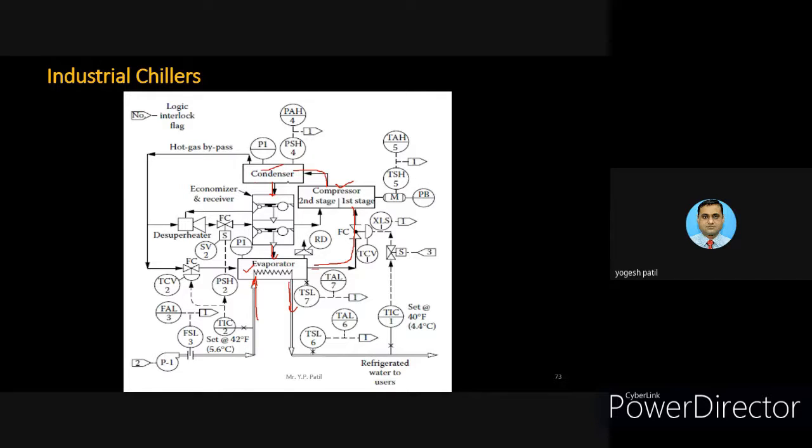And you can see that in the condenser part the cooling tower lines are not mentioned. When we focus on this basic block diagram, you can see there is an additional line from the condenser that enters the de-superheater also, and the same can enter through a valve into the evaporator also. These additional things, in more detail, are there to improve the efficiency.